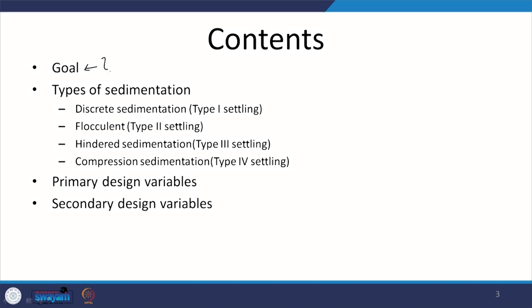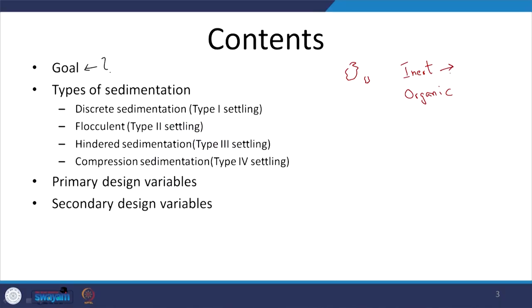Let us look at what we want to achieve here. We have suspended particles — relatively bigger, some smaller — some of these are inert and some have organic content. If inert particles are not removed, they will cause issues down the line in other unit processes by settling out, leading to relatively lesser effective volume, and can also lead to abrasion and wear of relevant machinery. The bigger or heavier inert content is removed during preliminary treatment or headworks, but there will be some suspended particles smaller than grit, along with suspended organic content.